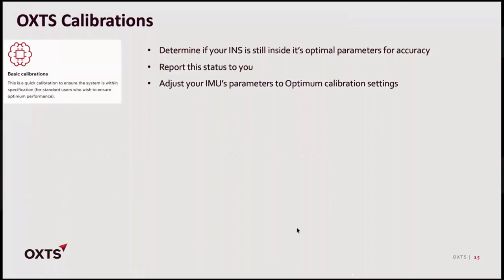And then just the last thing I'll cover quickly is, as I mentioned, within those 3 different calibration services, just to make sure it's clear, if you get a standard calibration from OXTS, we're going to start by seeing where is the performance of your current system? Is it within the accuracy that we would demand for our systems? We report that back to you as a finding, but we also adjust back to optimum before we send that unit back to you. So you get an understanding of where your unit was when you shipped it back to us, but really importantly, you always know when it comes back, we've readjusted it back to optimum performance.